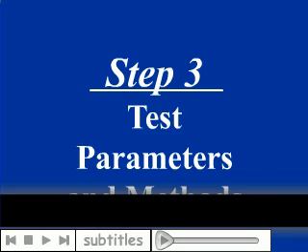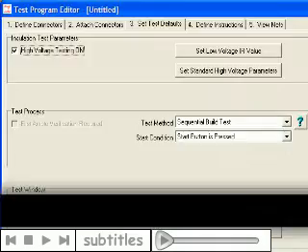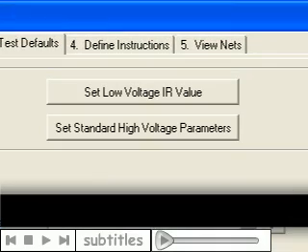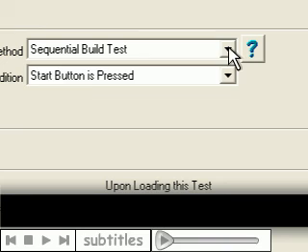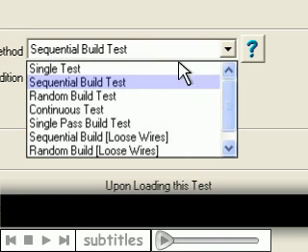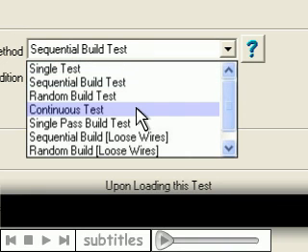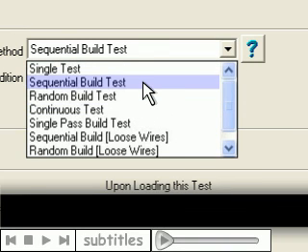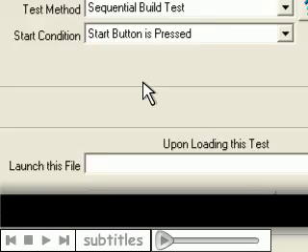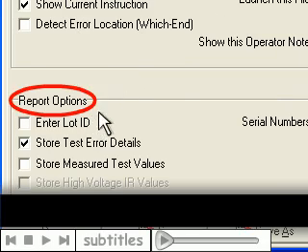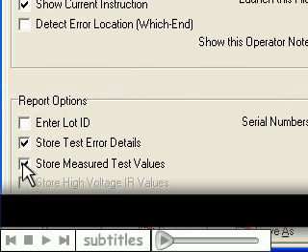You then set the test parameters and methods. These include low and high voltage test settings, test processes such as single test, continual test, or build and test mode, and report options and SPC data collection methods for this test.